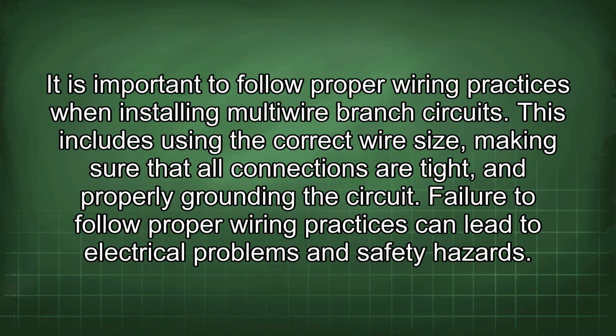Tenthly, proper wiring practices. It is important to follow proper wiring practices when installing multi-wire branch circuits. This includes using the correct wire size, making sure that all connections are tight, and properly grounding the circuit. Failure to follow proper wiring practices can lead to electrical problems and safety hazards.